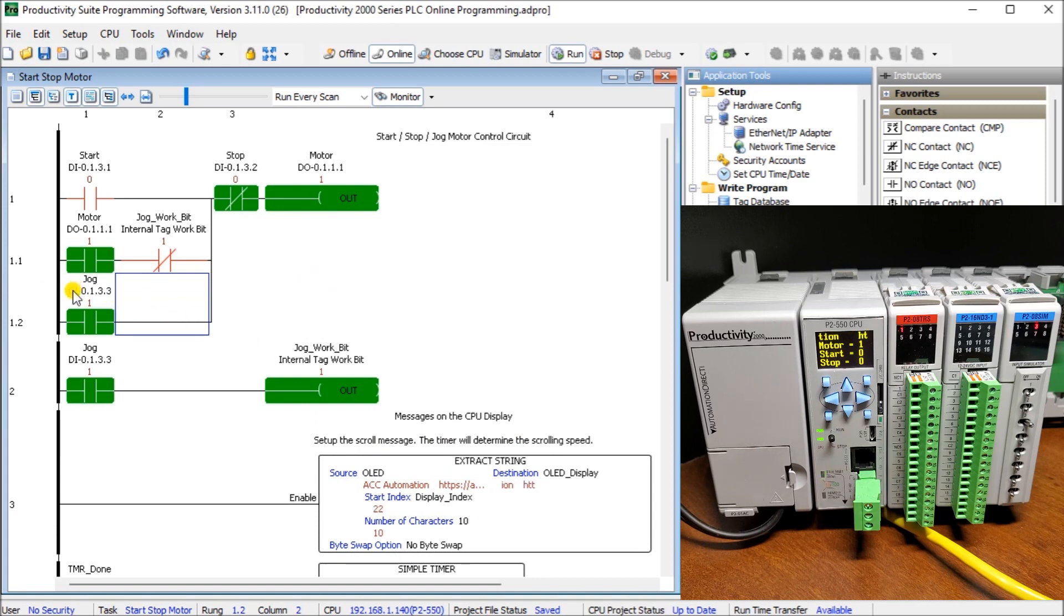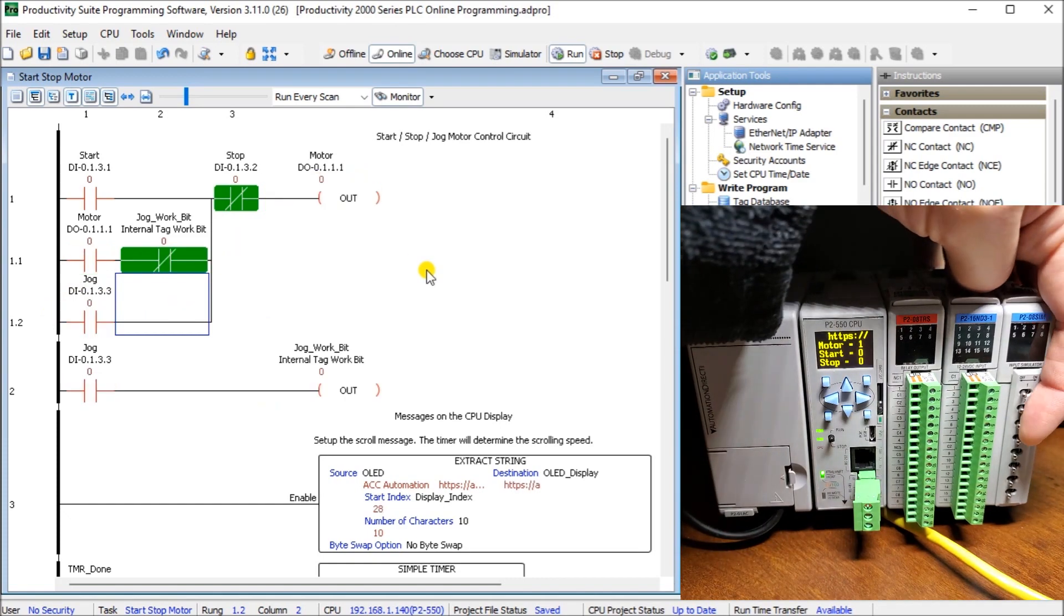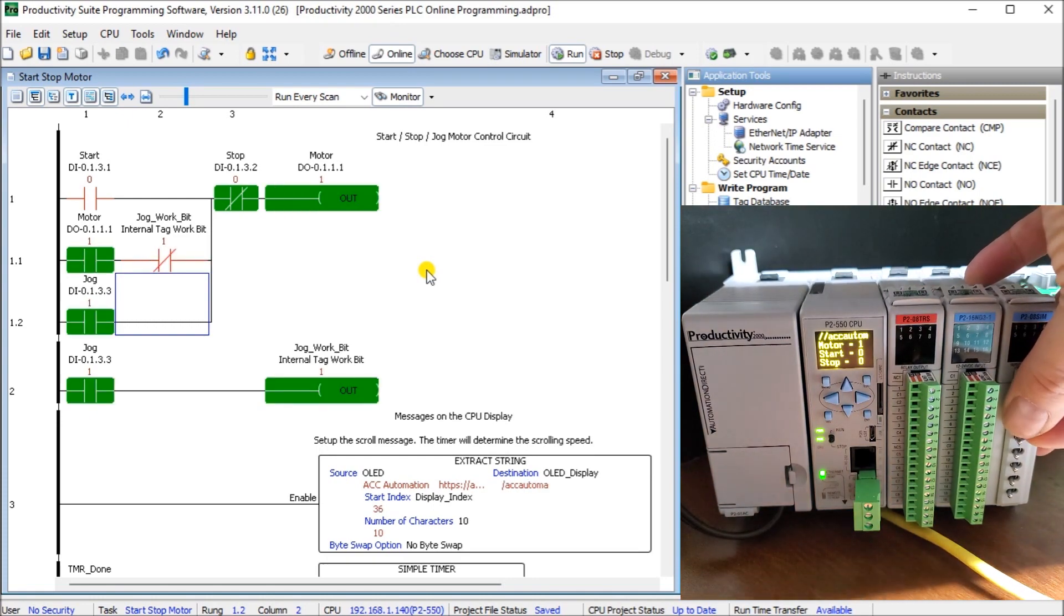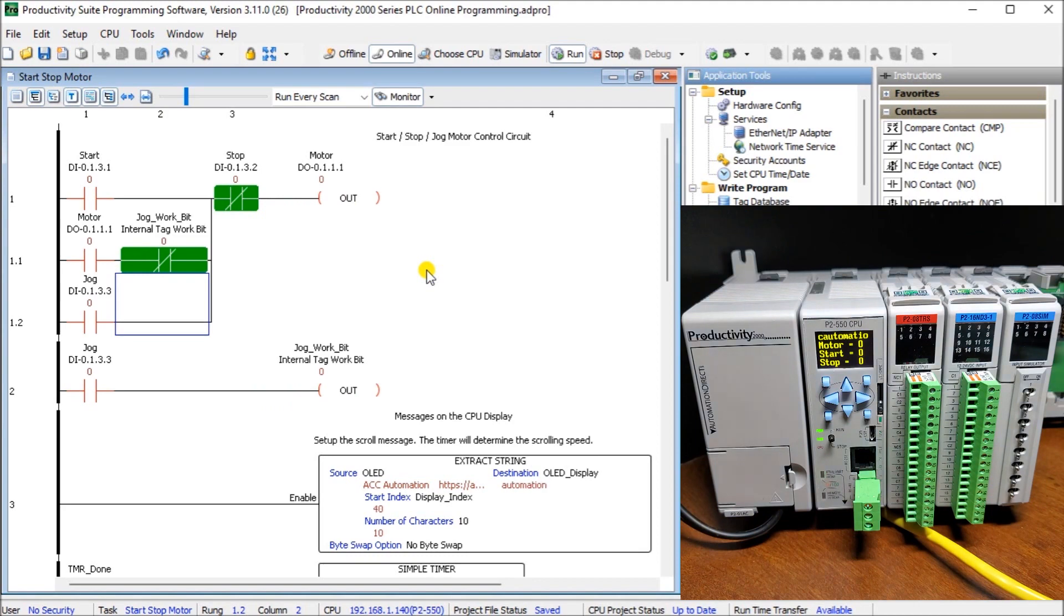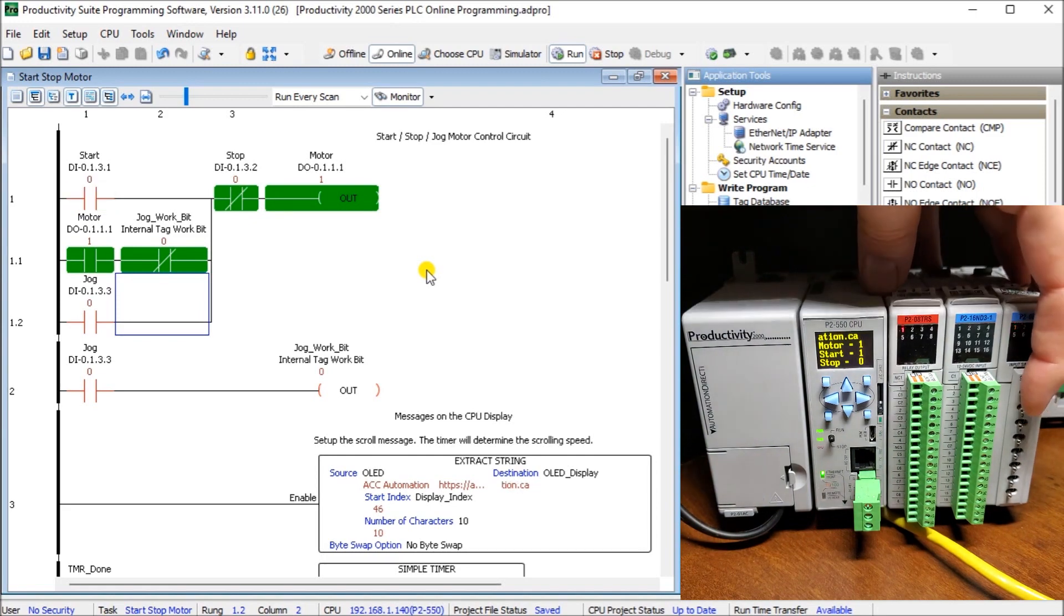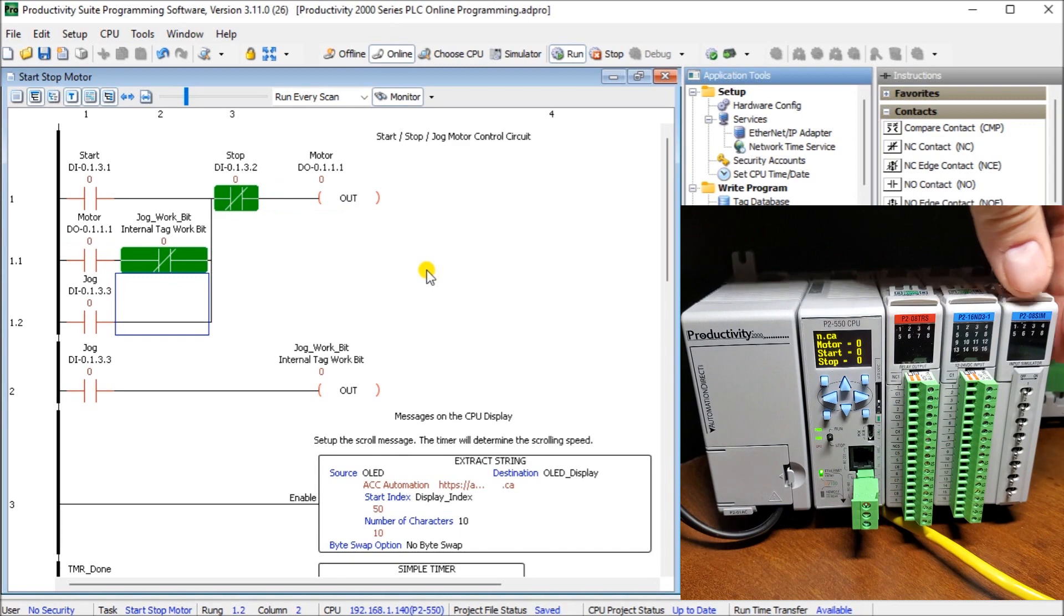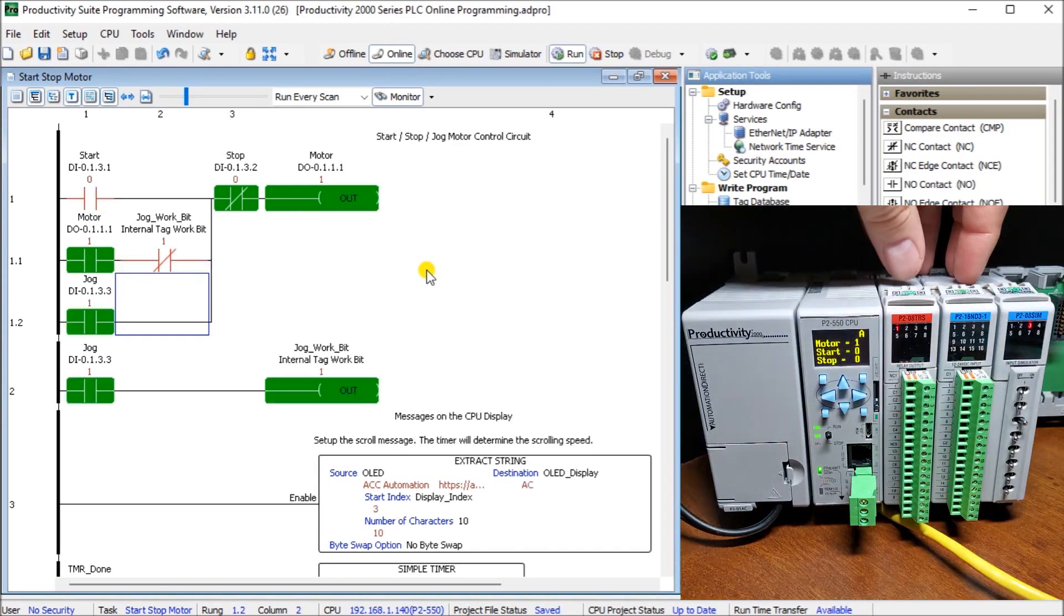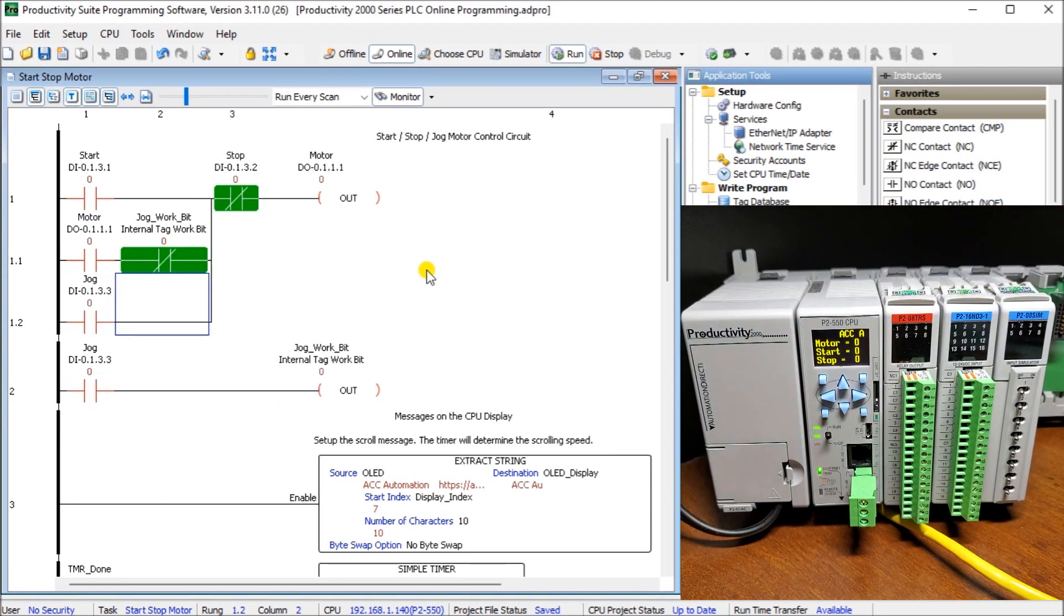You'll notice that first of all our JOG bit came on right away because that's what the program is actually doing. The JOG bit's on so the output comes on. If I turn the JOG bit off then the output then turns off. So the JOG actually goes with the output. All my other functions still work. There's my start and my stop. Or if I have my start and I have my JOG it remains on. If I turn off the JOG it turns off that motor.